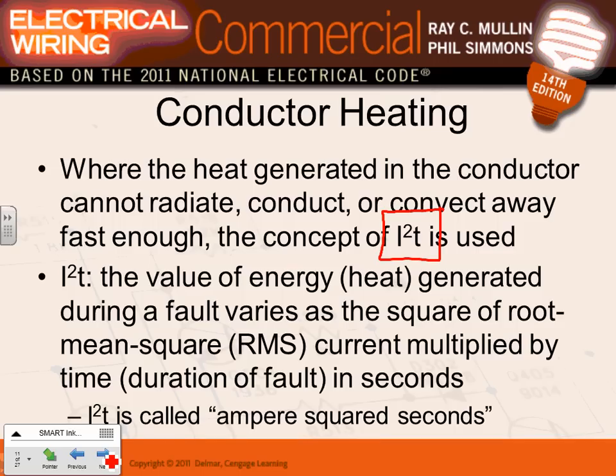Okay, so Jeff, my friend, I'm going to take my example here. I'm going to put this one into the same thing, 400 amp. This is my conductor, which is my baby here. I need this one, 500 kcm. I have a short circuit right here, guys, in this conductor. And this short circuit is, let's just say, 21 kiloamps. Can you guys see it, 21 kiloamps? Let's see how much energy, heat, this 21 kiloamps is going to generate in this conductor.